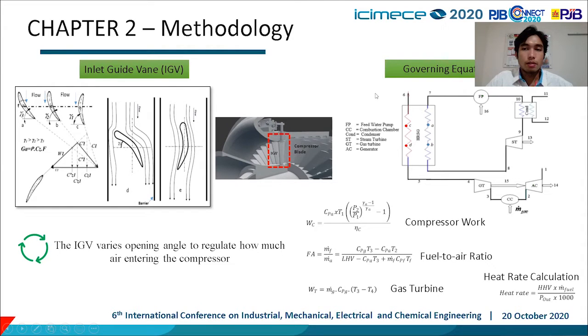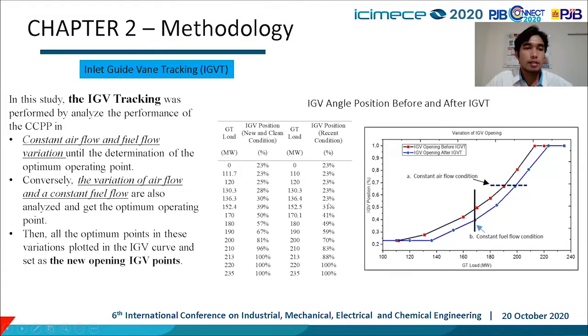In the right section is the governing equation used in this paper, consisting of compressor work, fuel to air ratio, gas turbine work, and heat rate calculations. The inlet guide vane tracking. In this study, the inlet guide vane tracking, or IGVT, was performed by analyzing the performance of the combined cycle power plant in constant air flow and fuel flow variation until the determination of the optimum operating point. Conversely, the variation of air flow and a constant fuel flow are also analyzed to get the optimum operating point. Then, all the optimum points in these variations are plotted in the IGVT curve and set as the new opening IGV points.